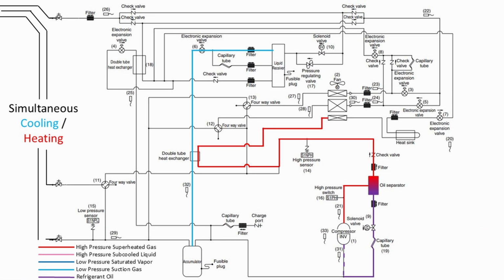This system is capable of taking some refrigerant off of the top of the liquid receiver, sending it through an expansion valve, and then directing it through the other side of the tube-in-tube heat exchanger to help subcool the refrigerant before it gets to the outdoor coil. As the refrigerant passes through the outdoor heat exchanger, it is subcooled into a liquid.